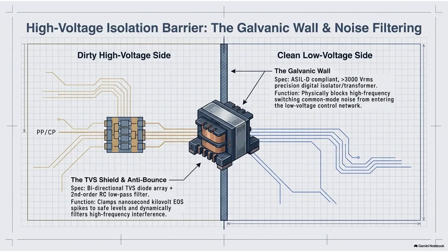So you have to separate the grounds. You have to build a wall. Exactly. Galvanic isolation is literally an electrical moat. There is no physical conductive wire connecting the high-voltage measurement side to the low-voltage logic side. The circuit board is physically split in half. To pass the critical communication data across that gap, they use something like an optocoupler.